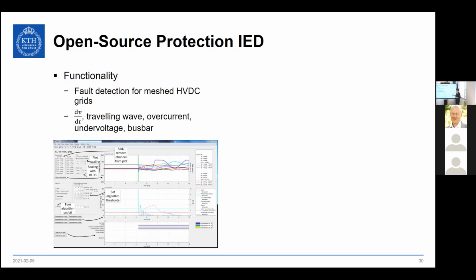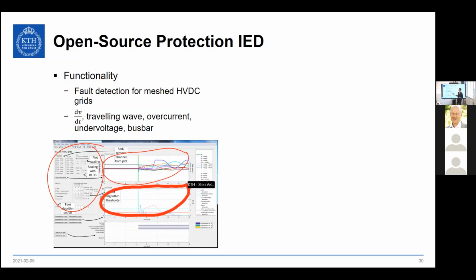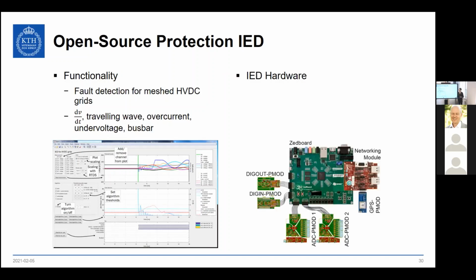Here you can see the graphical user interface you can use to connect to the IED with all kinds of settings: a window where you can read out the IED transient fault recorder, a window where you can see the fault detection signals compared to threshold, basically the margins, and then also a window where you can see the IED fault detection times for different algorithms.